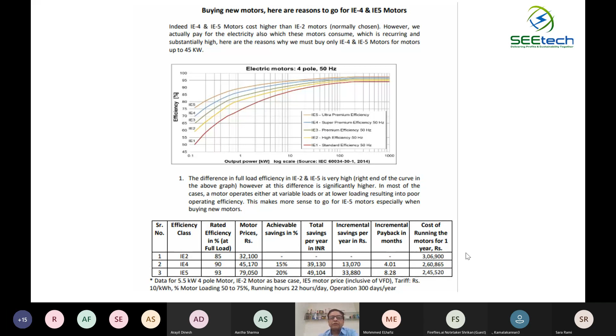The benefits of going for IE4 or IE5 motors are phenomenally high, whether it's a new motor case or a retrofit case. The only thing is that you need operating hours more than 8 hours per day. Because if your load is operating just 1 hour per day, there's no point in changing that.